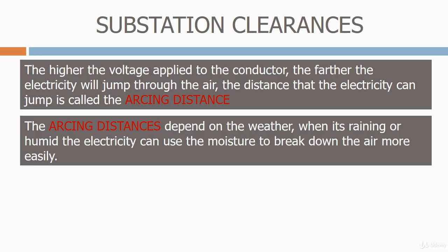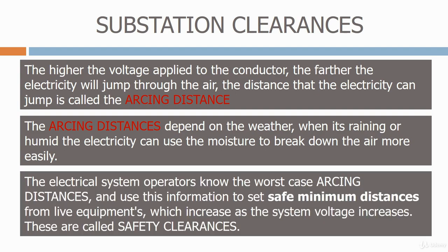The arcing distances depend on the weather. When it's raining or humid, the electricity can use the moisture to break down the air more easily. The electrical system operators know the worst-case arcing distances and use this information to set safe minimum distances from live equipments, which increase as the system voltage increases. These are called safety clearances.